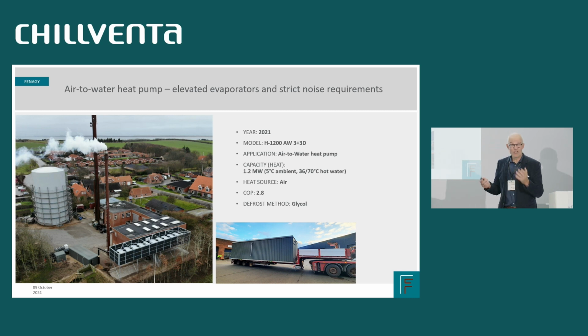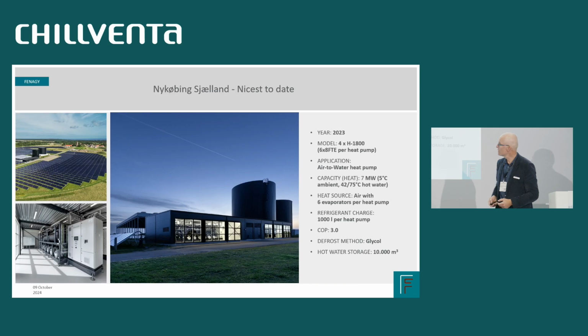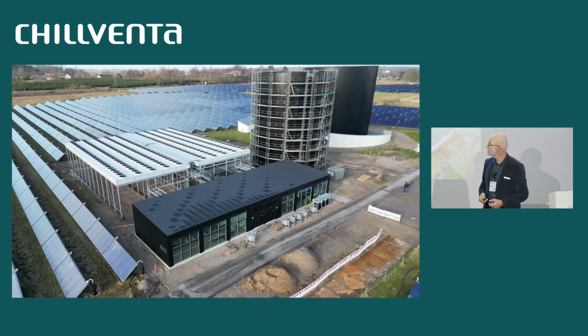But a lot of the district heating companies are in the middle of cities. The city grew around the district heating company, and now we're installing heat pumps. And the energy collectors are here. The heat pump is actually inside that box, because you didn't have space for it inside the building. Yes, this is a 7 megawatt heat pump. And again, a lot of vessel capacity here, and the heat pump's inside a nice building there.